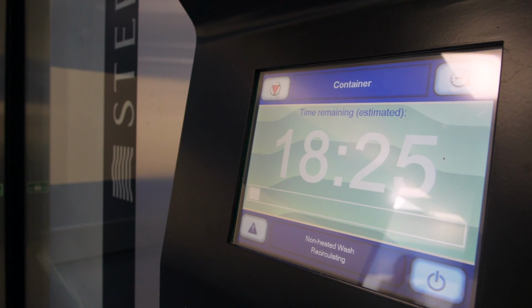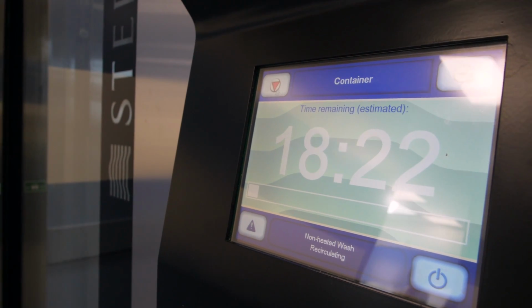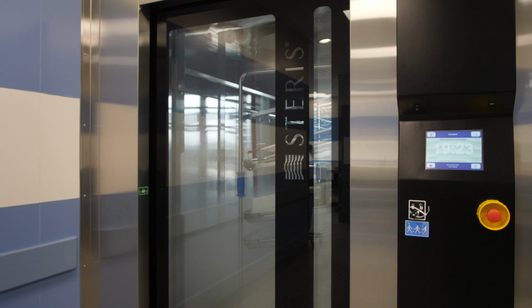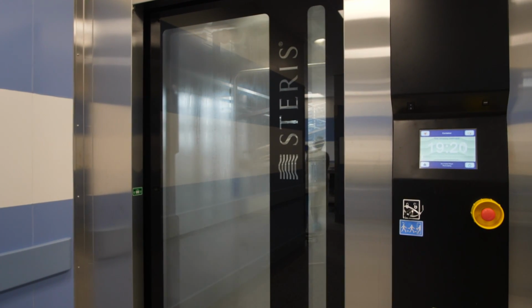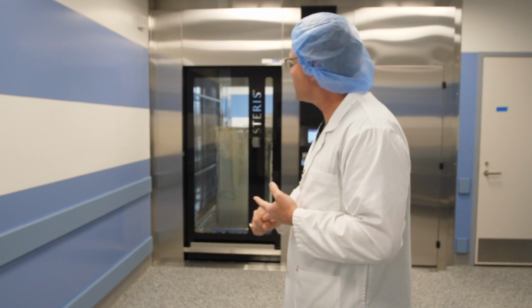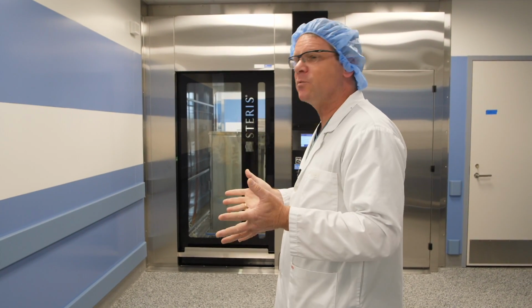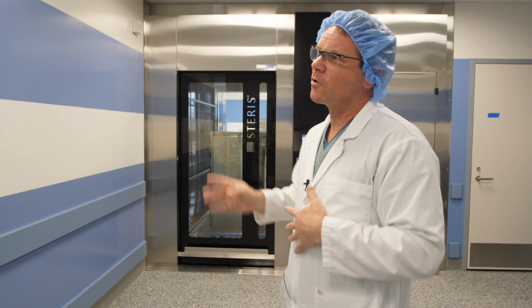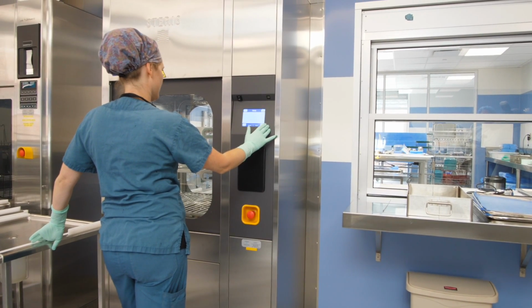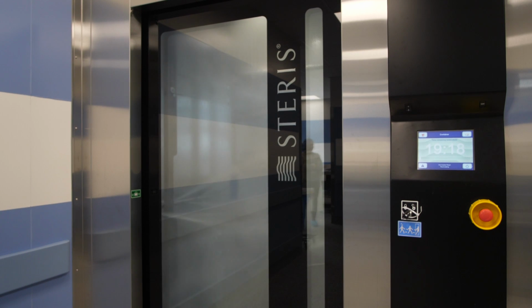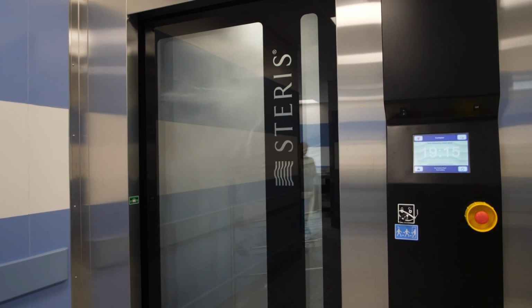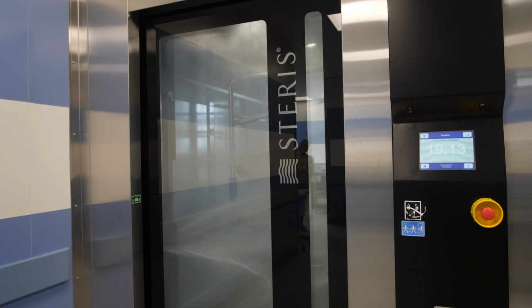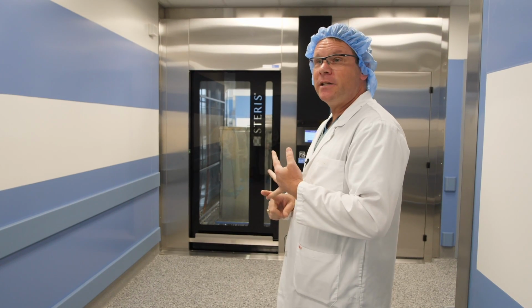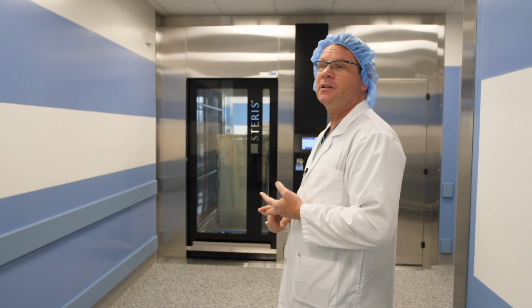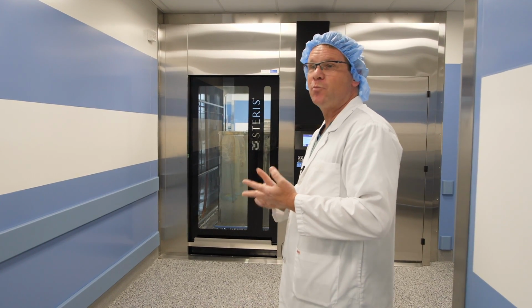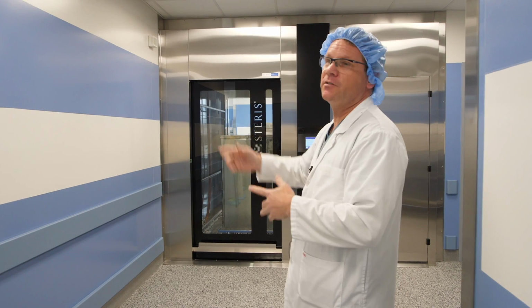And I'm so proud of this. This is the most amazing piece of equipment this hospital's had, in my opinion, aside from the CT scanner. This is able to wash carts. It's able to do all of our equipment that we use, all of our stainless steel, all of our bowls. In the past, everything that was done for this hospital, from emergency to our ortho clinic, was done out of one of those smaller washers. And now we have the capacity to do everything in a much larger washer. So we're able to increase the speed at which we get our sterile supplies back to our patients and into the areas of this hospital that need them. There's enzymatic cleaners, there's descaler, and there's a bright and shine cleaner so that everything comes out lubricated, pre-cleaned, and ready for the sterilization unit.